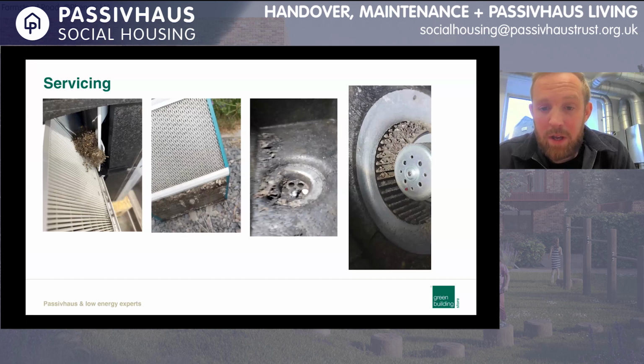We've then got a condensate drain in the bottom of the unit. During the heat transfer process, condensate is produced and it drains away to an internal drain point. Mold does build up gradually in there, so that needs checking. And what we'd do to check that is firstly we'd clean that one because it is quite a build-up, and then we'd pour a glass of water down that drain to check it's still draining sufficiently.